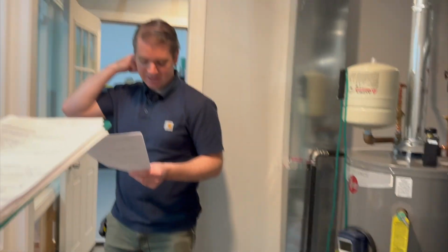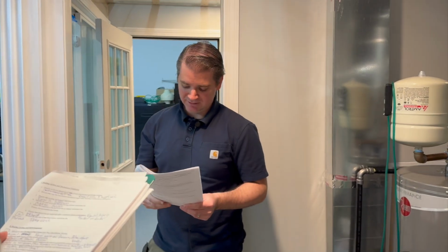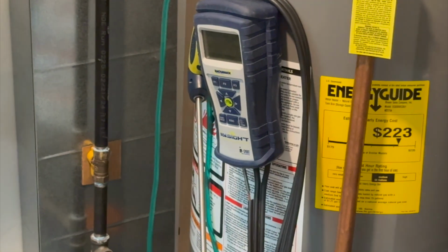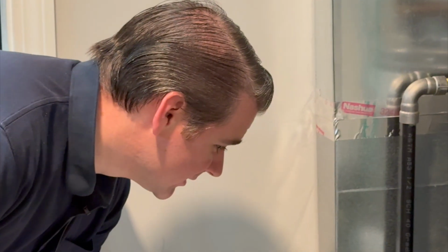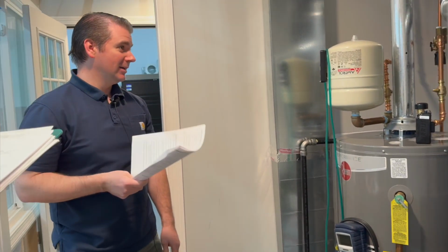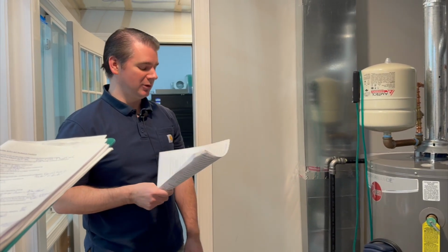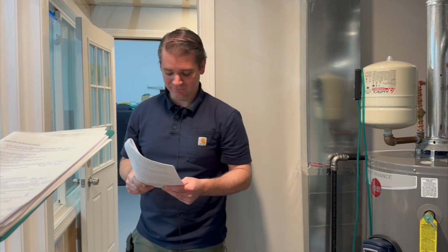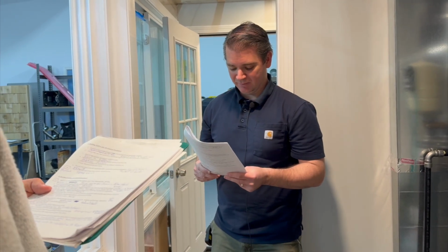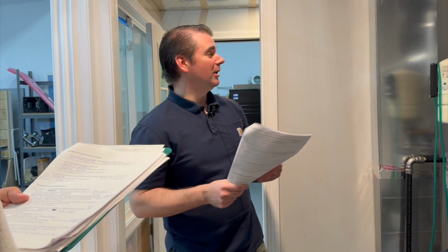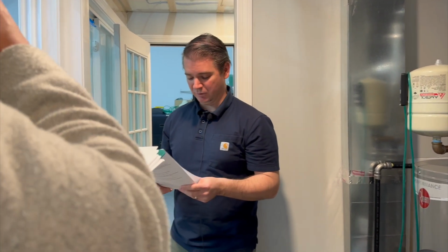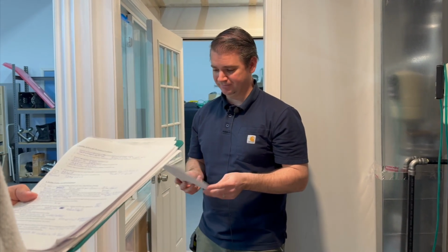Describe opportunities for adding water heater insulation based on the nameplate or manufacturer's specifications. Well, the nameplate doesn't really mention anything here about insulation. I can see it's internally wrapped with insulation. We're inside conditioned space, so I wouldn't recommend adding insulation for this water heater. Identify and discuss opportunities for domestic hot water pipe insulation. Well, our water pipes are going up into the attic, so it'd definitely be worthwhile to insulate those hot water pipes to prevent wasted energy.